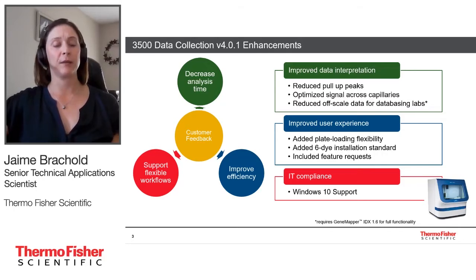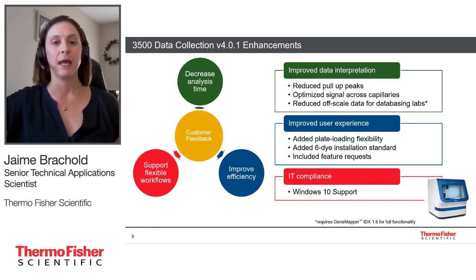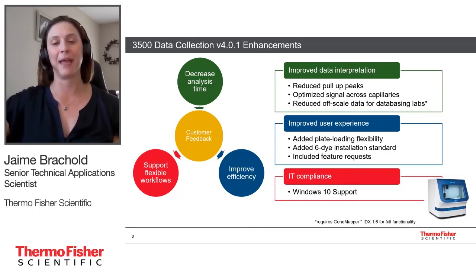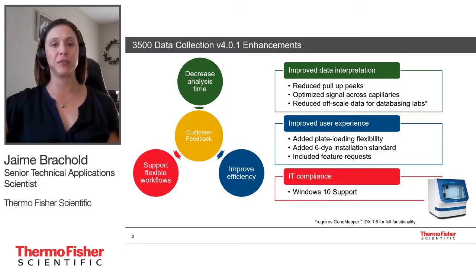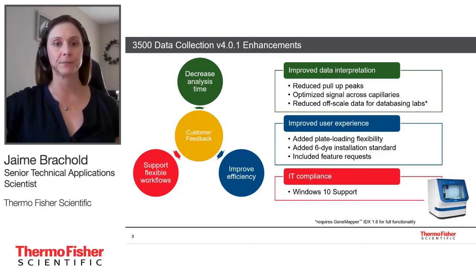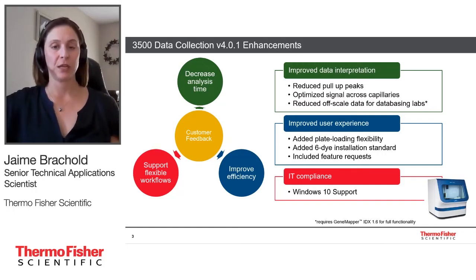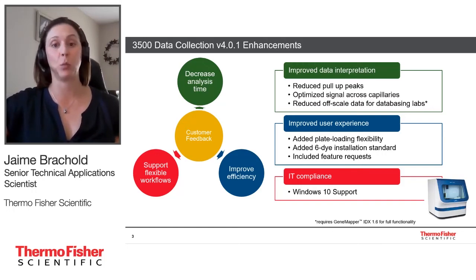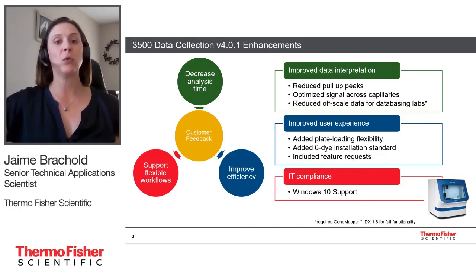We also optimized signal across the capillaries in two ways. On a 24-cap system, we introduced a spatial optimization to account for optical variation across the 24 capillaries. On both the 24 and 8-cap instruments, we have a recommendation for a Z-offset — a higher position in the well when the capillaries go in for injection — which can be performed by an engineer during a routine PM or auto-sampler calibration. We also introduced an algorithm for reducing off-scale data for databasing labs or those running robust single-source reference samples.